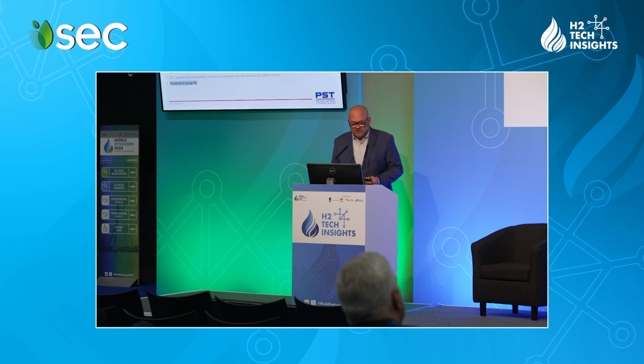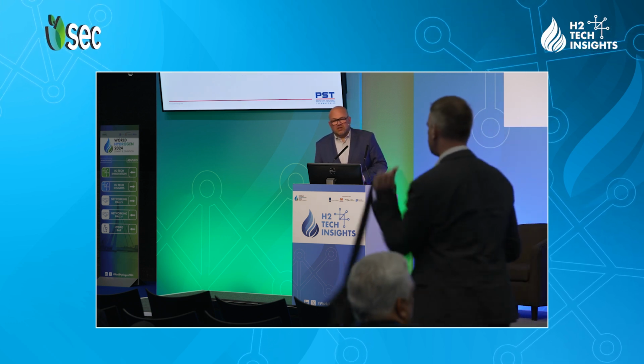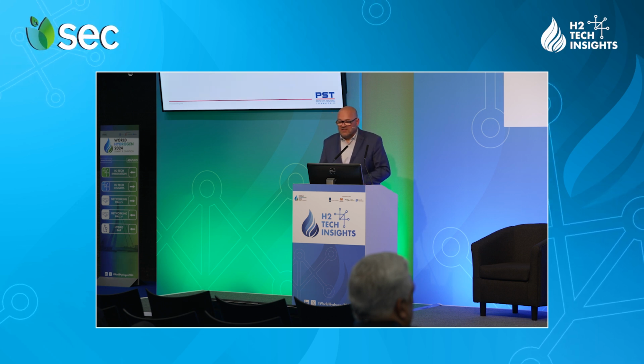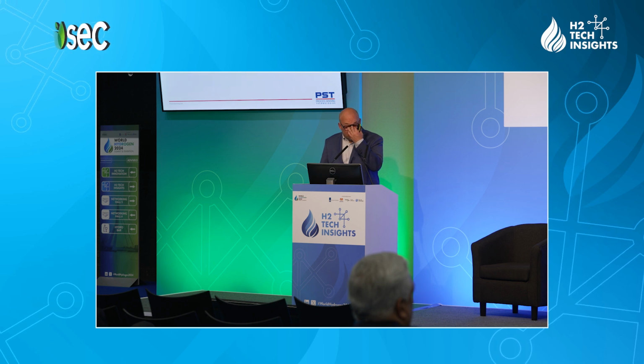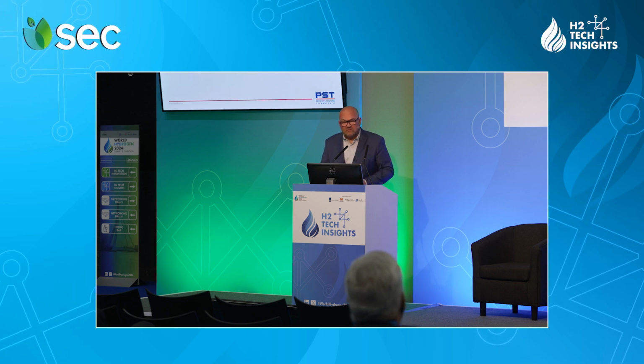Then there will be a presence of purged nitrogen. We need to deal with that as well. So then we go to the next topic, basically. For the oxygen in hydrogen measurement, purged nitrogen in the hydrogen gas. Electrolyzers are purged with nitrogen at commissioning, after maintenance, when things are being opened up. Some people do this all the time, not doing maintenance all the time, but purging between operation for safety precaution.